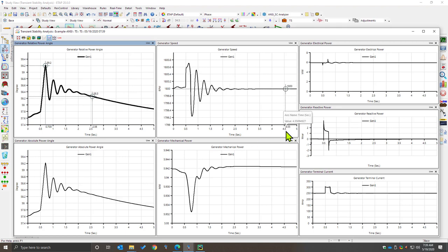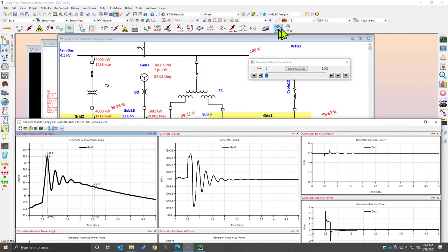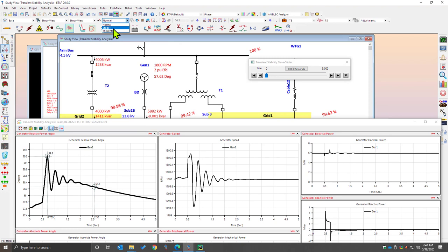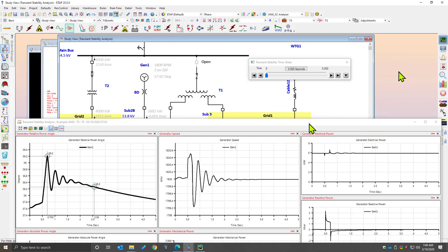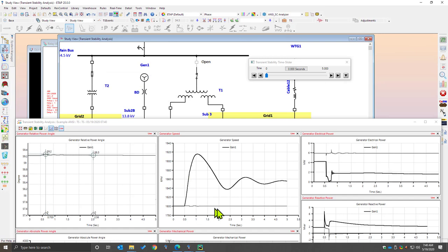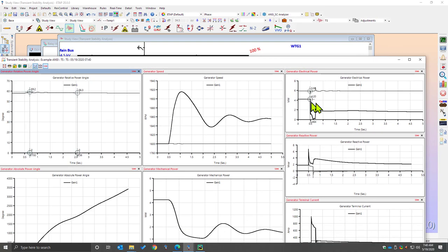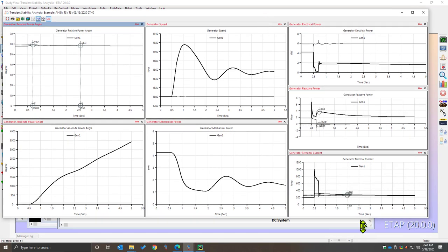When you print this chart, all this information is printed along with it. To see what live view does for us, we click on live and switch over to a completely different configuration of the system where a particular breaker is open. Running our transient stability calculation in live view, the previous result is kept and the live information is added to the chart as well. The previous information is shown in a lighter color and the new information is in the darker color, so you can quickly evaluate what is happening during the study and see the difference from the previous run to the current run.